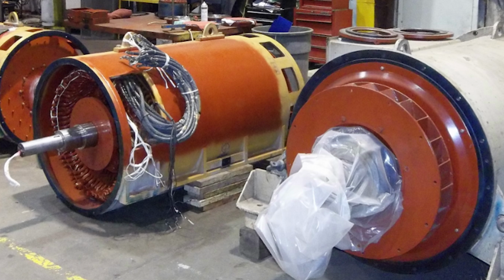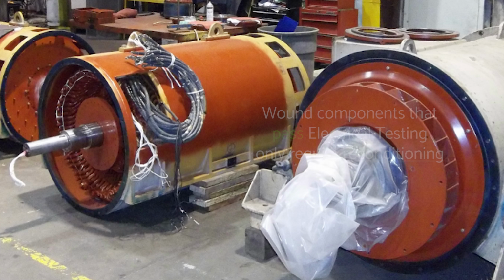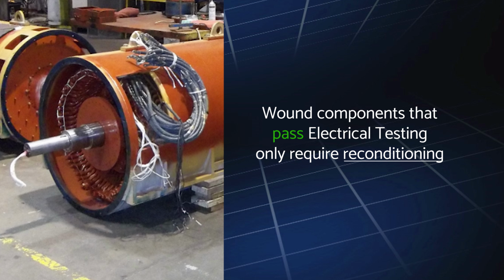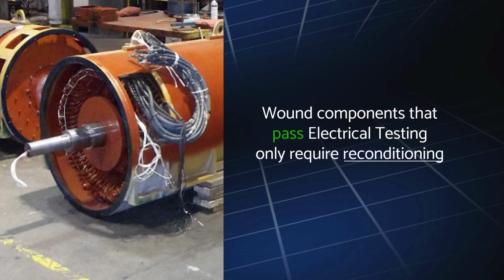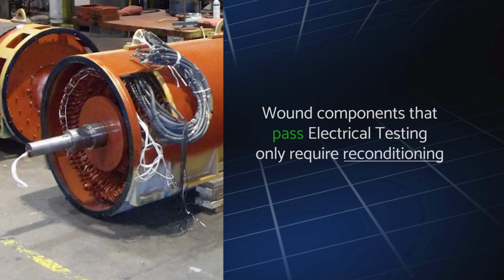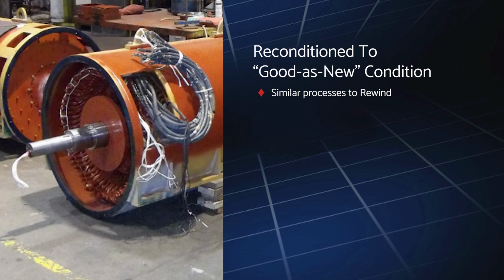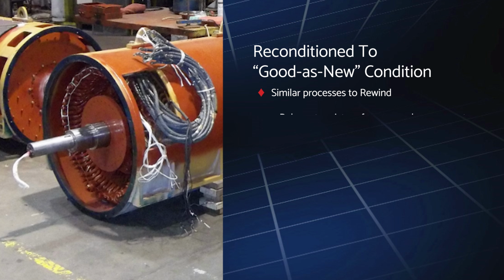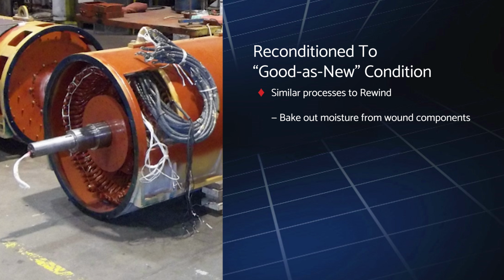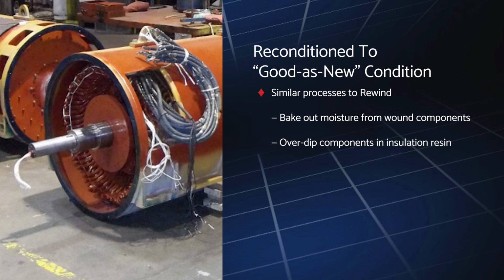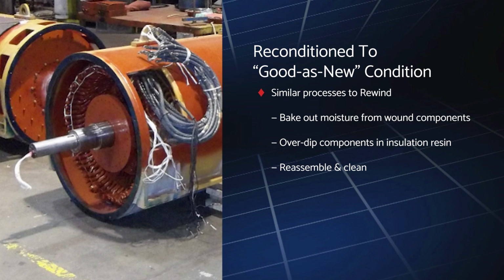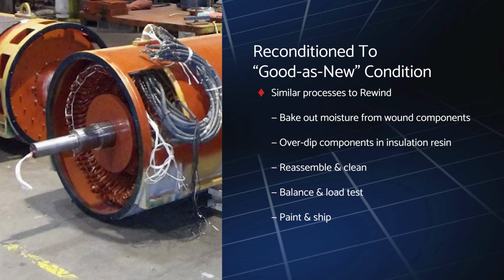Motors and generators that pass initial electrical testing are typically designated a recon, where the equipment only needs to be reconditioned to good-as-new condition and not otherwise repaired. Recons follow many of the same processes as rewinds, including baking out the moisture from the components, dipping the wound components in insulation resin, reassembling and cleaning, dynamic balancing and load testing, painting, and shipping.